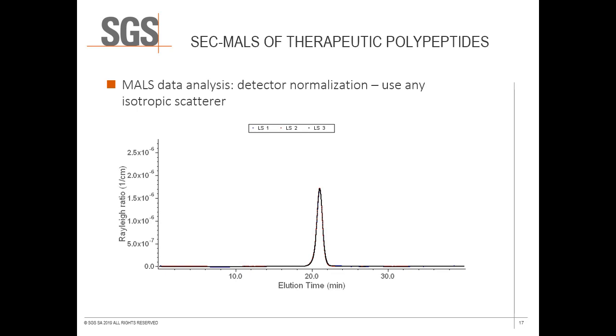While some labs who perform only a single analysis repetitively on their SEC system may find it suitable to normalize their MALS detector signals only occasionally, we are changing SEC columns, solvents, and sample types constantly, and so we perform band broadening, alignment, and normalization corrections with every analysis. These correction factors are applied to the configuration of all sample data files. These corrections are easily achieved with the single well-selected polymer standard.